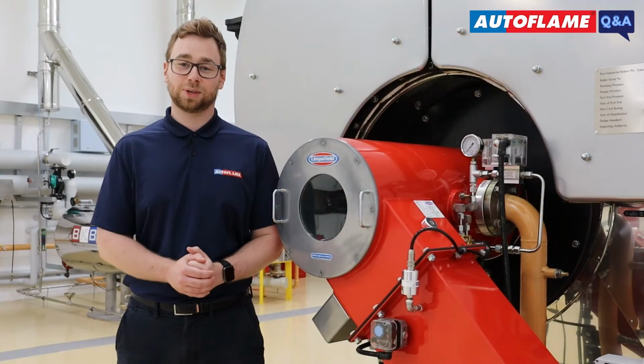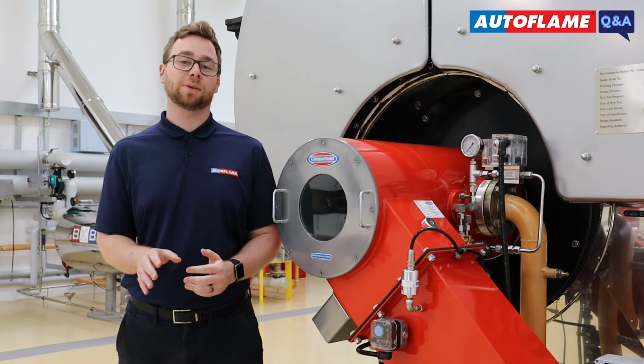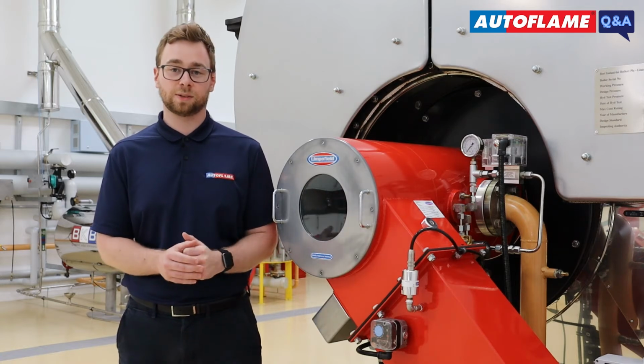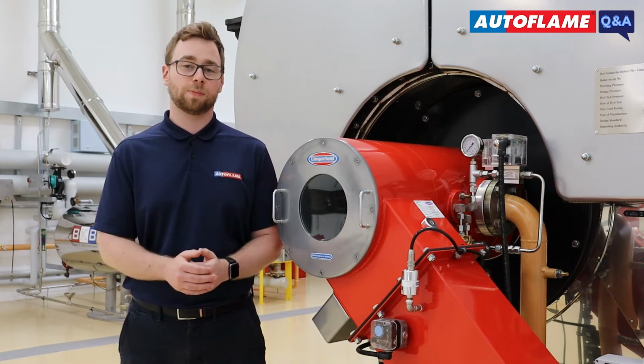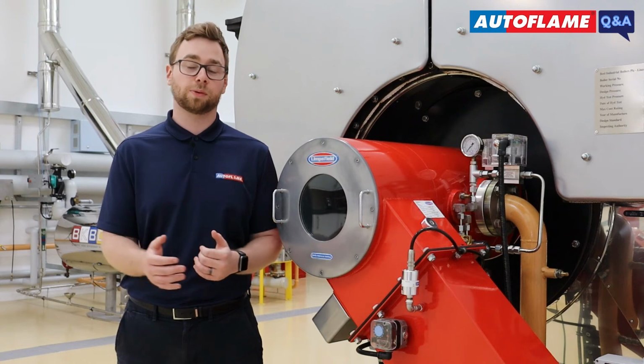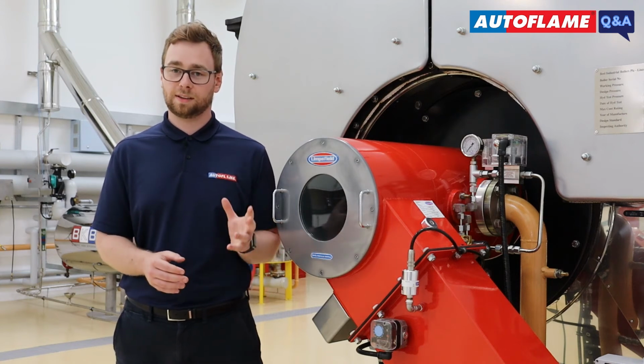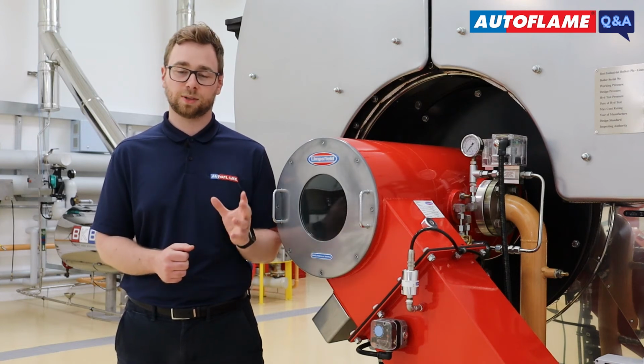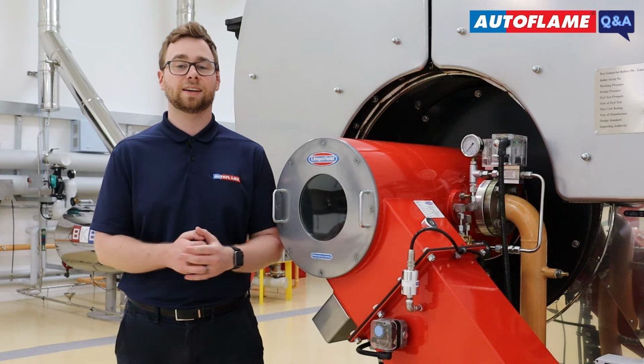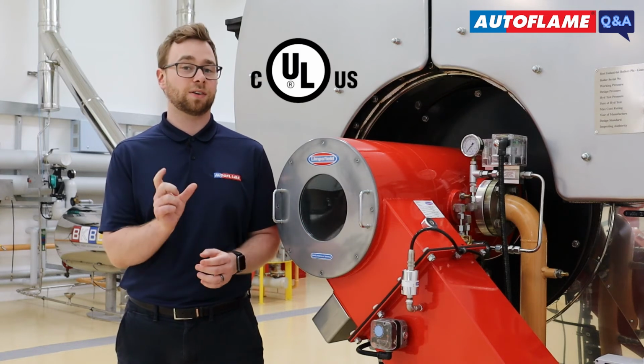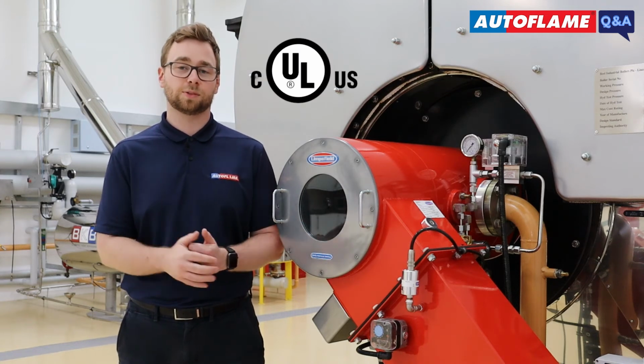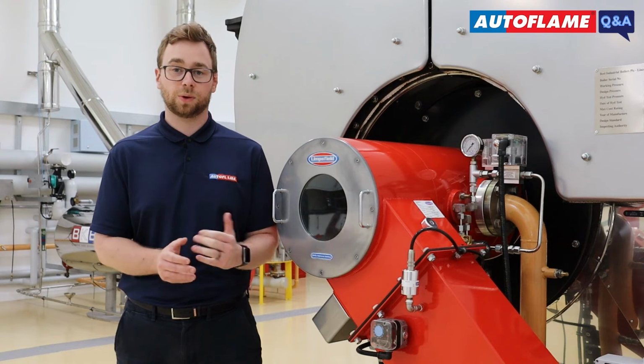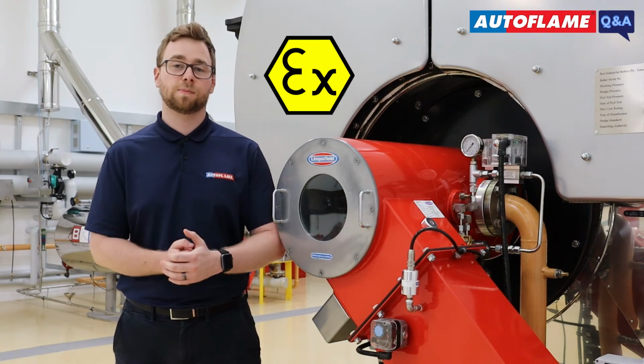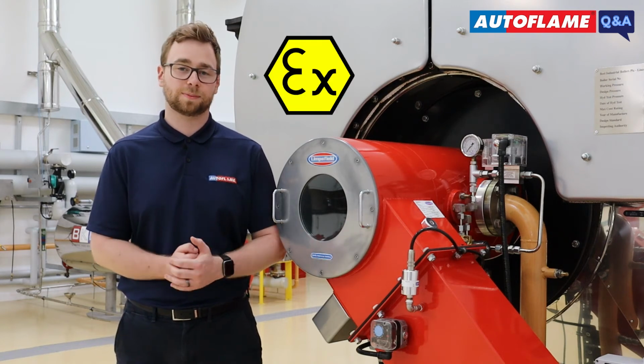A gas or air pressure switch will shut down the burner at a discrete value, whereas the Autoflame pressure sensors will generate a warning or shut down the burner at an offset from your commissioned pressure. Now, typically, an Autoflame gas or air pressure sensor will work in conjunction with your existing pressure switches. However, they are UL approved to work in place of a switch as a limit device. We can also provide an ATEX approved pressure sensor for hazardous environments.